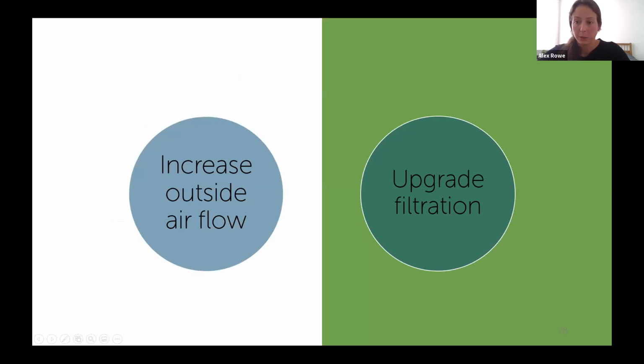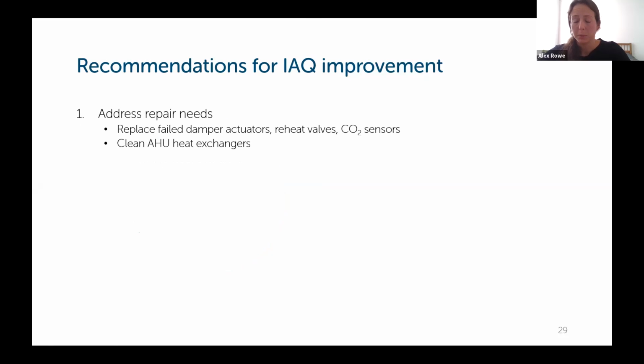So going back to those 2 pillars that Rachel mentioned for improving indoor air quality, increasing outside airflow and upgrading filtration, that's what the engineer was focused on as they developed their recommendations. So the first recommendation for improving indoor air quality was to address the repair needs that were identified. So replacing failed damper actuators and reheat valves and those CO2 sensors that were out of calibration, and cleaning the air handling unit heat exchangers to both maximize airflow and heat transfer.